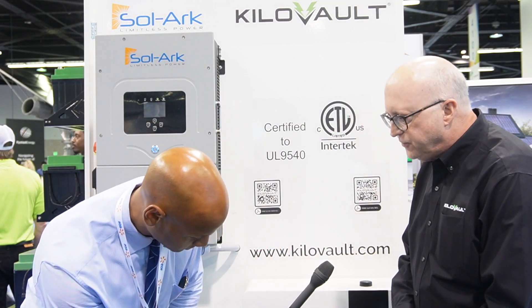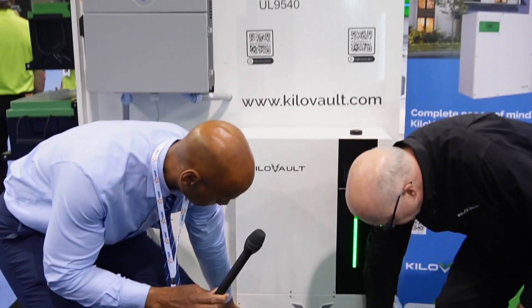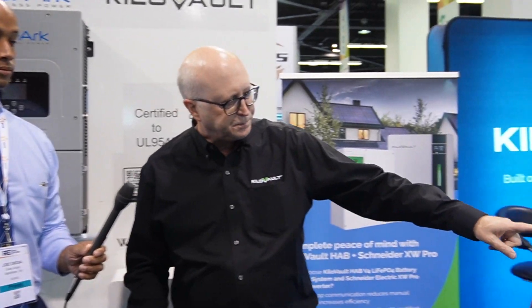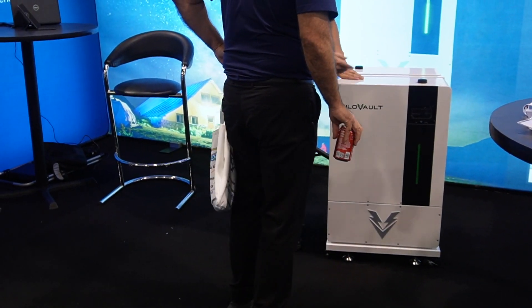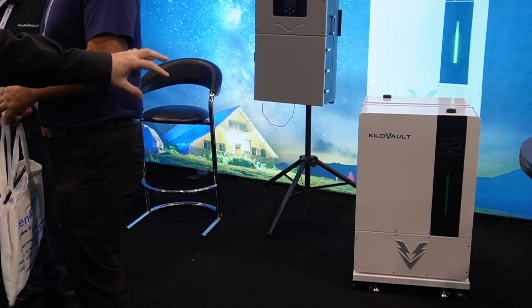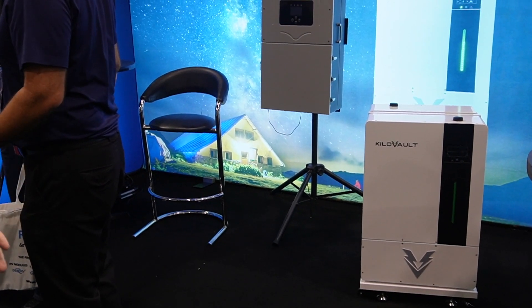Traditionally, we've had this hanging on a wall, much like the Sol-Ark is right here. That works for a lot of people, but some people want to actually just put it on the floor. So we've got this floor stand that lets it stay elevated — in case you have any minor flooding in your garage — and protects it from that. The wall doesn't have to bear the weight; the floor takes it. And over here, we have another mounting option that allows us to have two HABs on a cart, so you basically have 15 kilowatt hours right there. You could use several of those carts, giving you a very dense area to put a lot of storage.